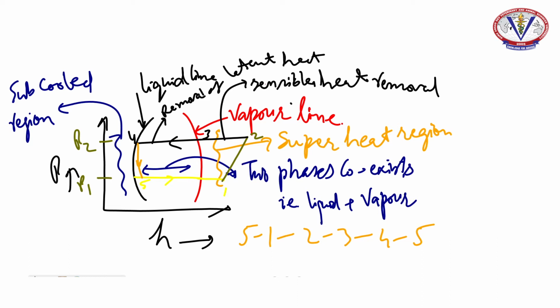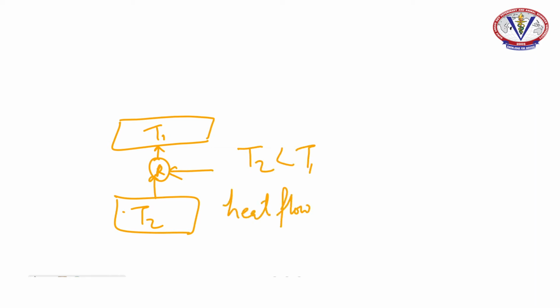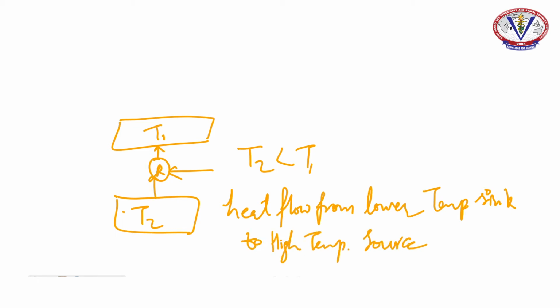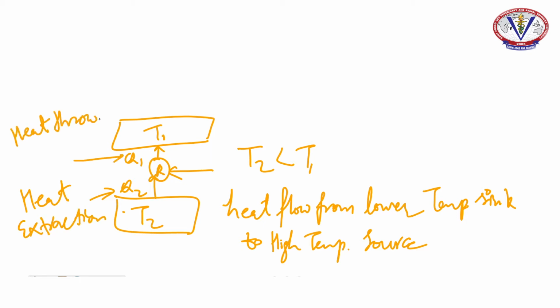From this p-h diagram we can clearly see the refrigerating effect and the amount of heat to be removed during the condensation process. Now this whole vapor compression refrigeration system indicates that the refrigeration system is working as a heat pump, which is taking heat from the space or the commodity which is already at lower temperature, and then throwing the heat to the environment which is already at higher temperature. So thermodynamically speaking, the heat is being extracted from the sink through a refrigeration system, and then heat is being thrown to the source which is already at high temperature.